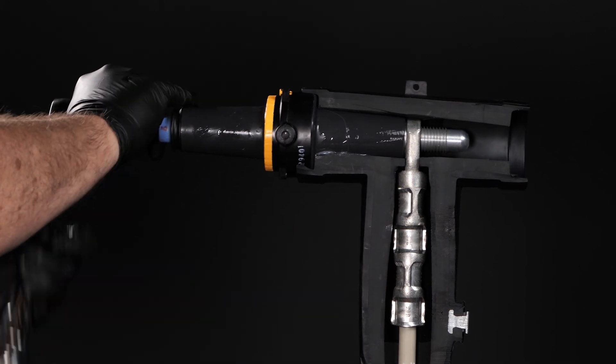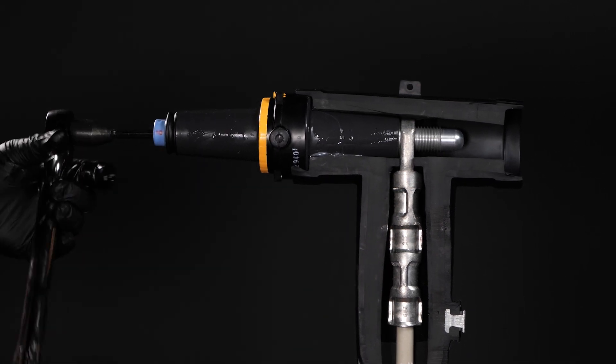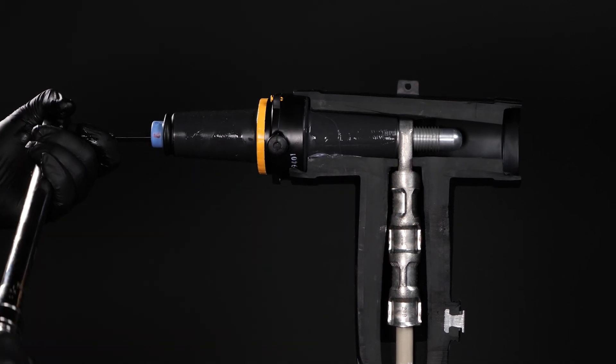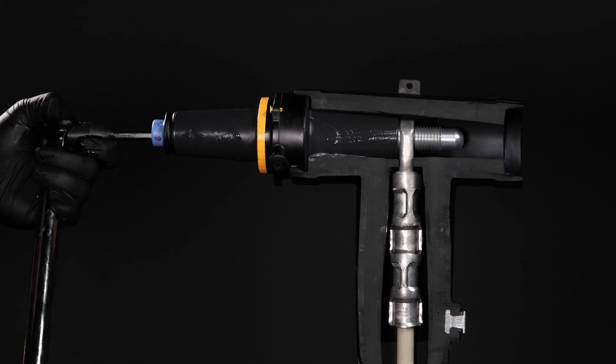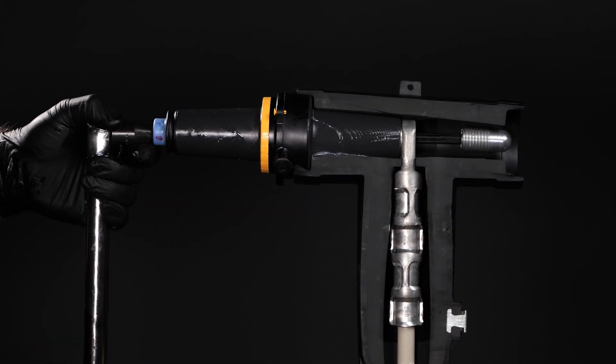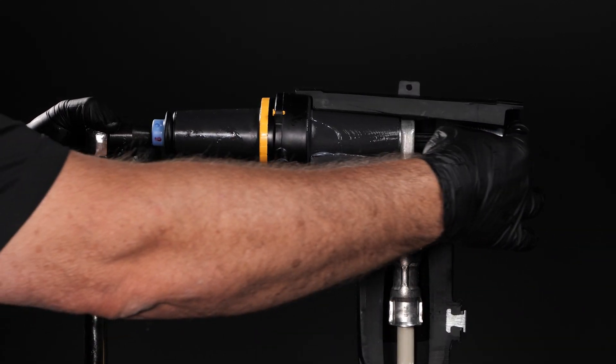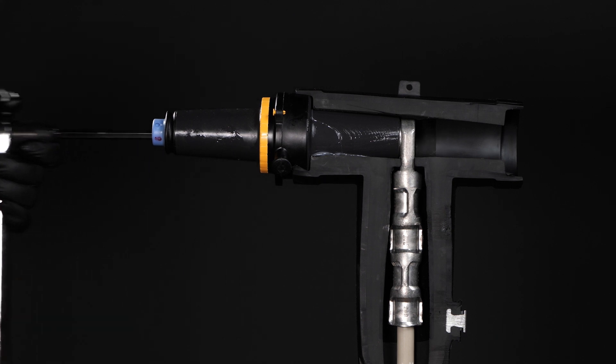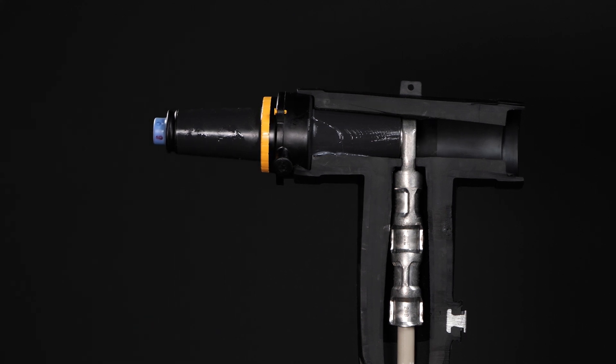The bullet nose will shear off once a torque of approximately 23 foot-pounds is achieved. There is a clean separation between the shear segment and the SureTap. Remove and recycle the shear segment.